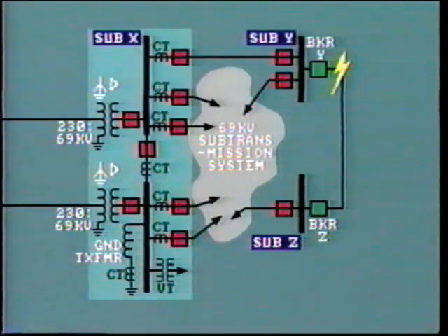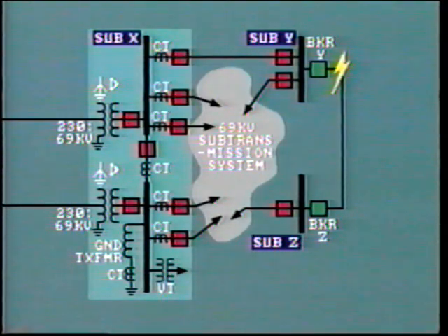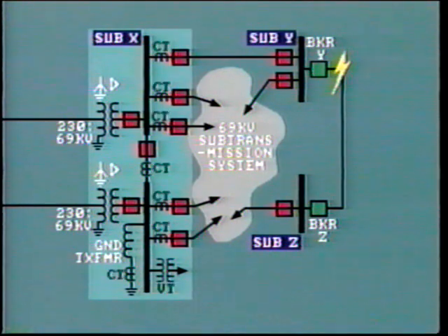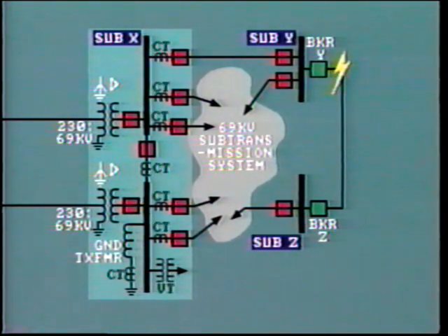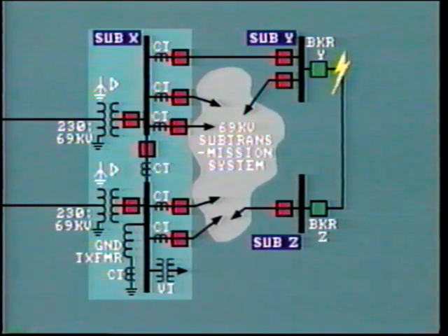This example has demonstrated two things. First, the nature of a fault can change during a disturbance, and in this case, the protection operated correctly to clear the fault. Secondly, our example showed that recording equipment located several buses away from the actual fault can still provide valuable information during a fault investigation.